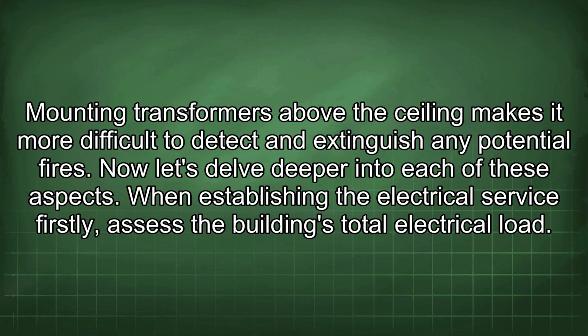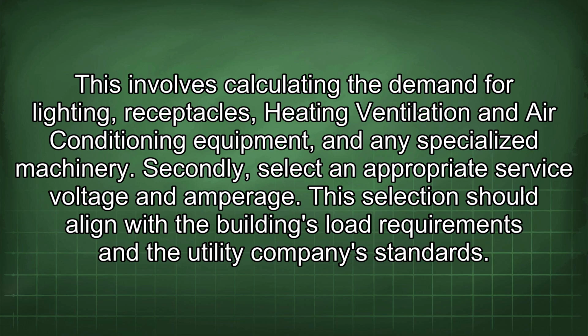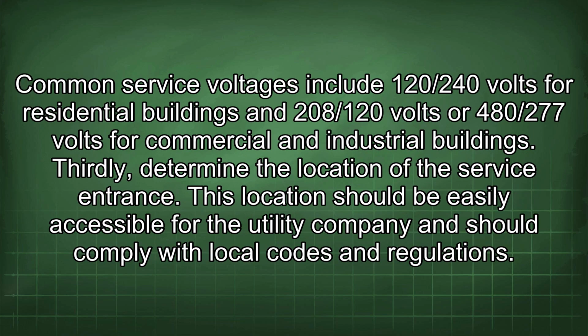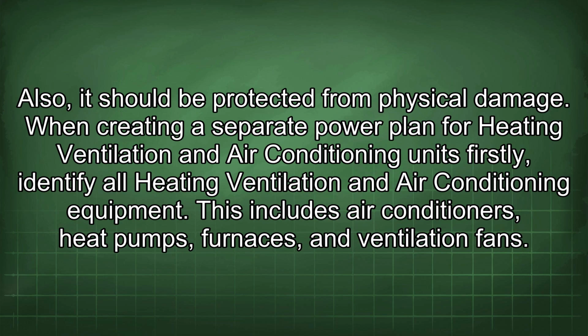When establishing the electrical service, firstly, assess the building's total electrical load. This involves calculating the demand for lighting, receptacles, heating, ventilation, and air conditioning equipment, and any specialized machinery. Secondly, select an appropriate service voltage and amperage. This selection should align with the building's load requirements and the utility company's standards. Common service voltages include 120/240 volts for residential buildings and 208/120 volts or 480/277 volts for commercial and industrial buildings. Thirdly, determine the location of the service entrance. This location should be easily accessible for the utility company and should comply with local codes and regulations. Also, it should be protected from physical damage.